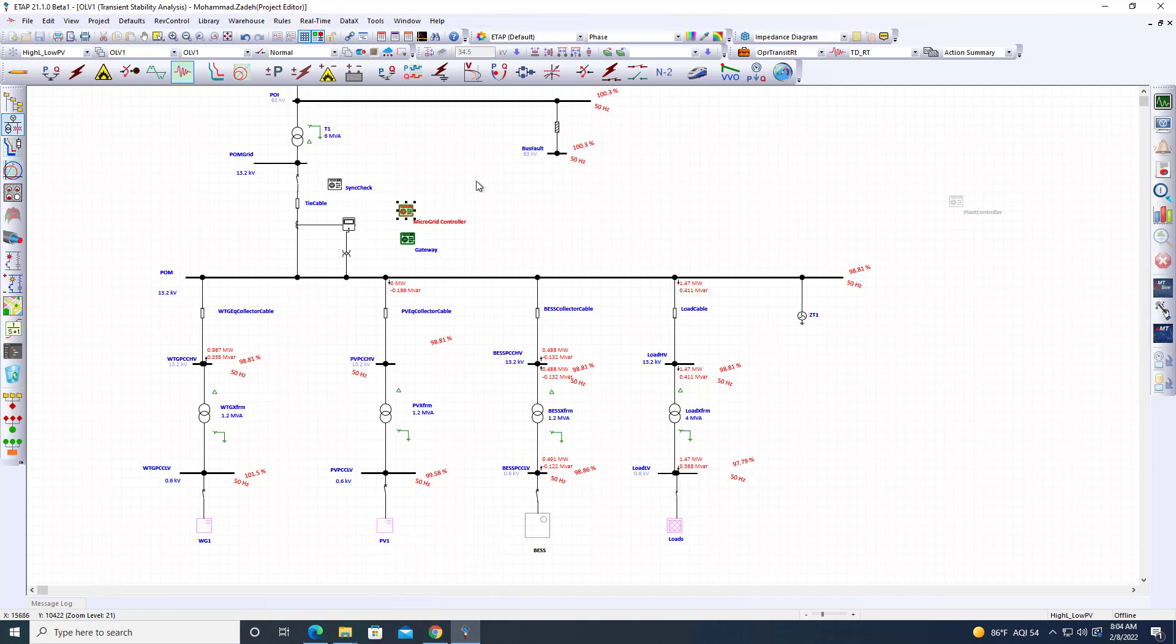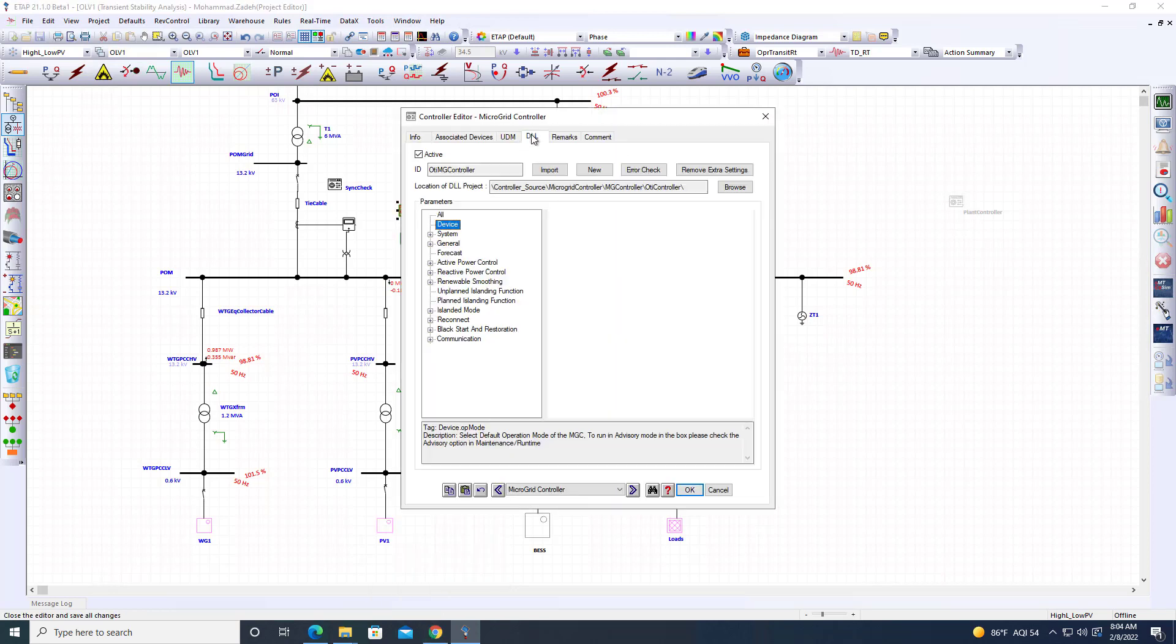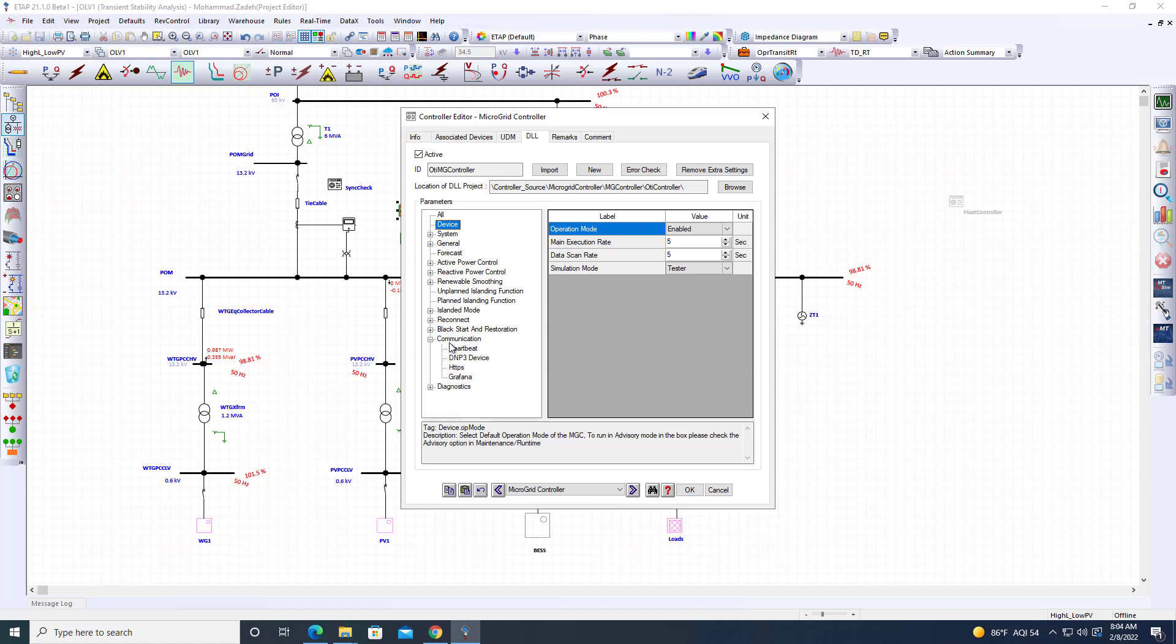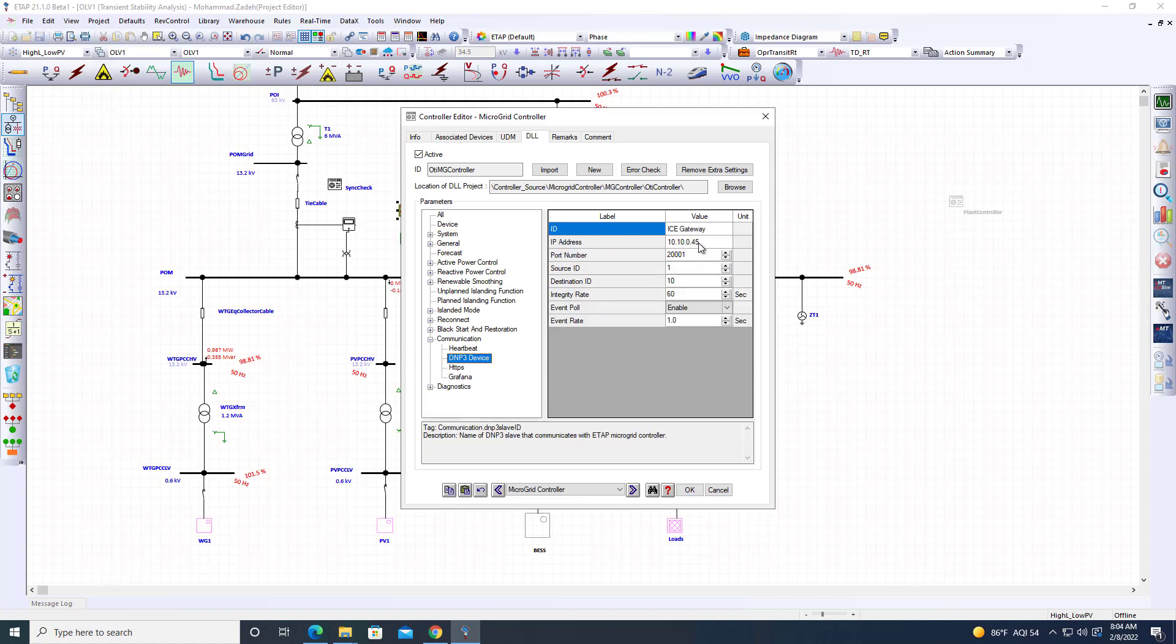The same logic that runs in the digital twin sends the output back to the microgrid. In the communication sections, we have the IP address of this device. We're going to use 20001 as a port number for DNP3. It has source ID, destination ID, some default numbers I'm not going to touch.